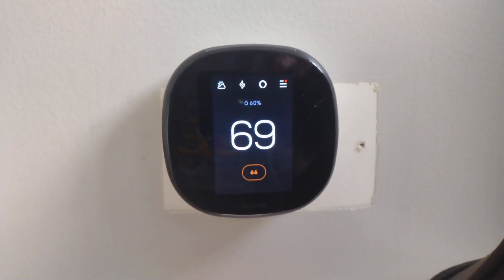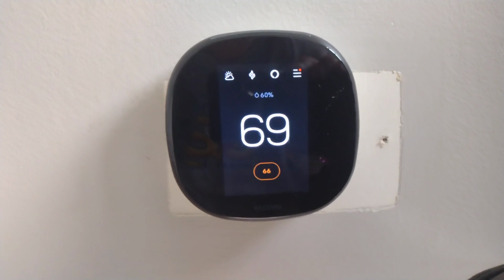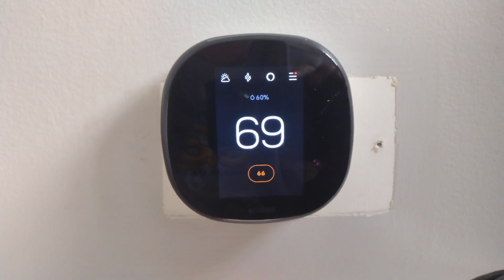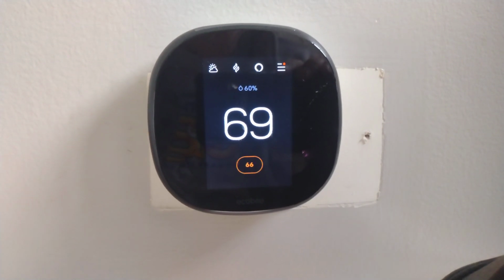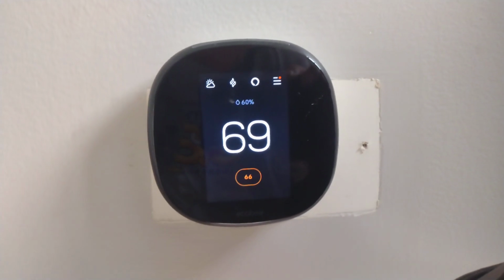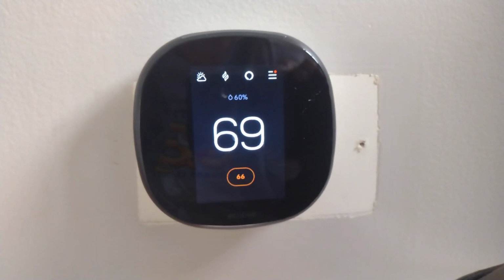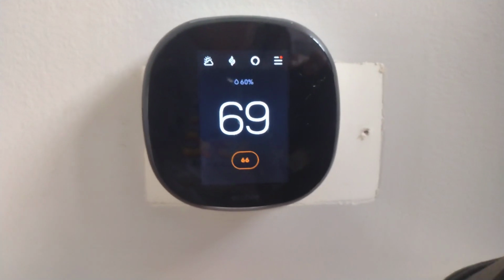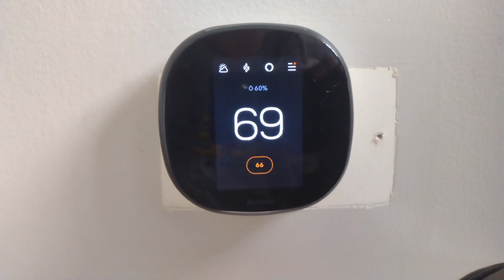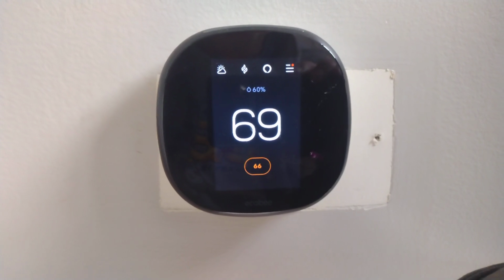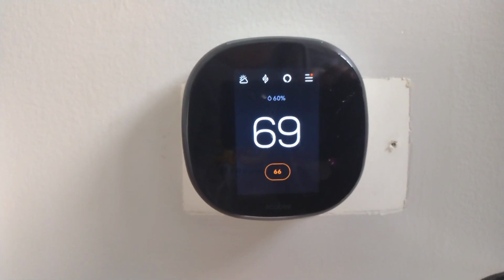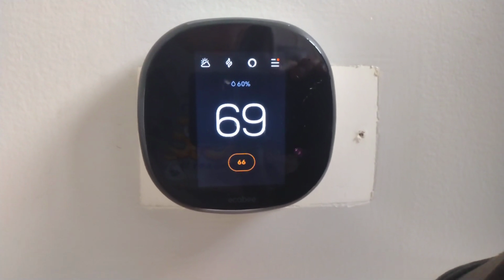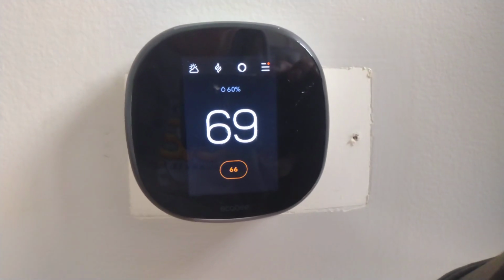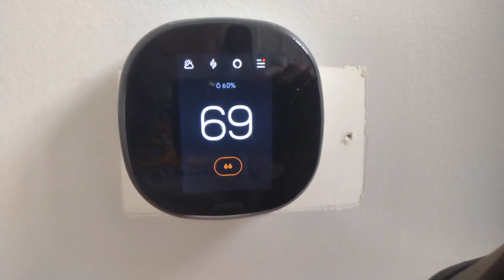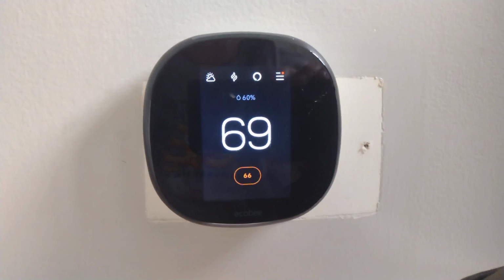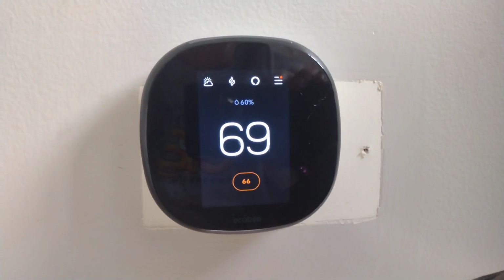In the smart thermostat premium, which is their most recent version of the Ecobee, that has the voice control and the air quality sensors. I found the air quality sensors to be inaccurate, and because when it sets off the sensor, it puts a warning right on the screen here. It started to concern people that there was a high CO2 reading in the house, like an Airbnb or short-term rental, that they were concerned about being in the house.